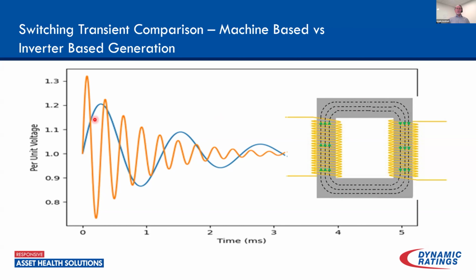Where if we have machine-based, it's not only lower voltage, but because of frequency, it's going to affect maybe a greater portion of that winding. So again, the stress when it comes to those inverter-based resources, with switching transients and things like that, is occurring every day as we bring these resources online and offline. And that's not even to say when they have failures and things like that. But the stress that these switching transients put on the windings, and bushings as well, has a significant impact on the increased failure modes that we're seeing.